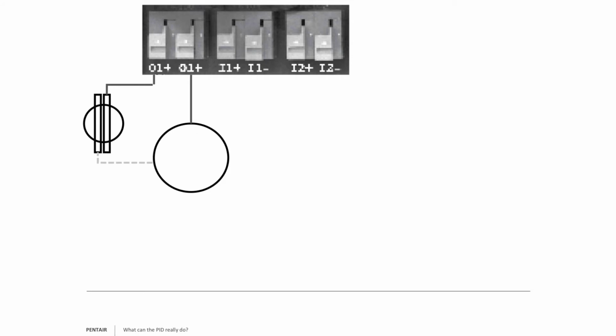So in this example, we are again using a lamp or maybe a siren and 115 voltage to charge it, and then use this to indicate the status of our unit. So here we have our plug-in pigtail from a 115 outlet going into O1 plus. Then we have the white of that cord going into one of the wires off the light bulb. The other side of the light wire, or the pigtail from the lamp, goes into O1 plus to complete the circuit. So now we told our unit that when the pump is running, I want that to close, and it's going to energize the bulb, giving us an indication the unit is running at the time.